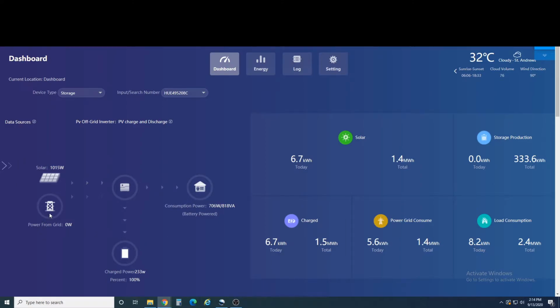In the little map over here you can see, since we've switched off the grid and are drawing from solar and battery, we currently have 0 watts coming from the grid. Unlike some inverters out there that can pull power from both the grid and solar/battery at once, this is one or the other — it can't pull power in from the grid at the same time it's supplying power, because these are not grid-tied inverters. They don't feed anything back; it either switches to the grid or from the grid, and when it switches from the grid there's no ability to feed anything back.